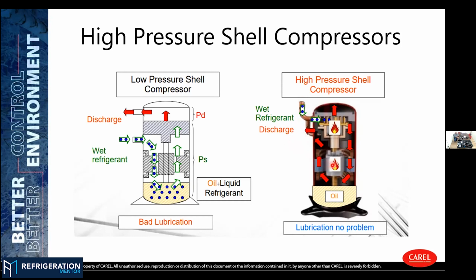And one last part that makes for me the most impressive part of this compressor: in general, when our compressors are vertical, the compressor chamber is on the top of the compressor. So we need to make the oil go from the carter to the compressor chamber in order to lubricate all the parts of the compressor. In a traditional compressor, we have some kind of pump that is attached to the rotor. So the limitation is you cannot decrease the speed too much because you will have some lubrication problems.